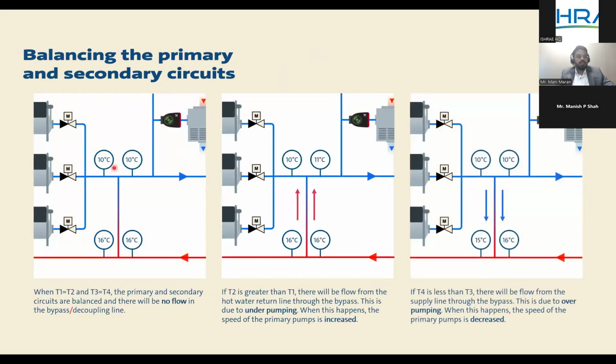To give an example, this is an ideal condition where your supply is 10, return is 16. Good. But let's say the flow is more on the secondary side. The excess flow will get bypassed through this decoupler. It's the least resistance path. So whatever the primary is capable of taking based on its speed, that flow will pass through, and whatever is excess will take the decoupler. The temperature, ideally supposed to be 10 degrees, is now increasing to 11 because of the excess flow. By identifying this scenario, the PLC or CPM will give a command to the primary pump to increase the speed, and the system gets balanced by itself.